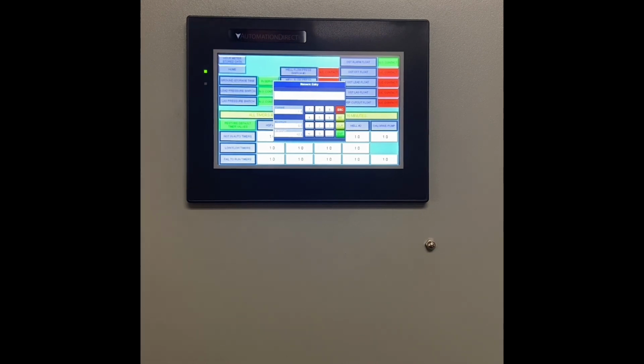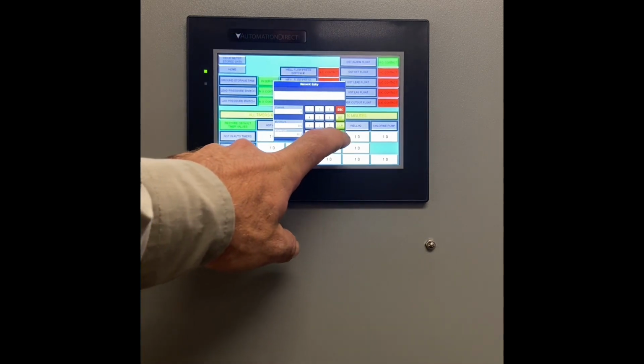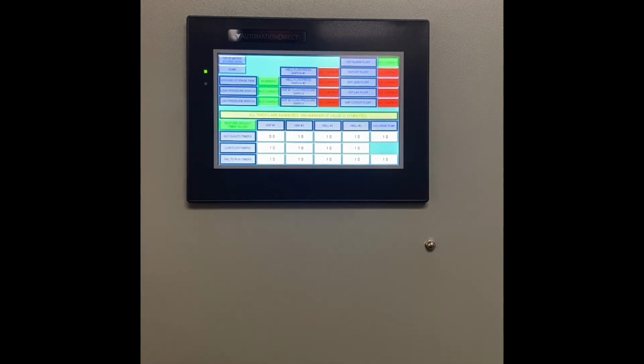The not in auto timer, if you're doing some control testing or system testing, you might want to have it out 2 or 3 minutes so it will not call for a pump. Not ideal, but I have been in situations where I've needed a little more time to work with a pump, and it's nice to have an easily adjustable time delay. Now, if I don't enter any value and I hit enter, I can have it at 0. That 0 value means that as soon as that pump is called for and it is not in auto, it will immediately fail.